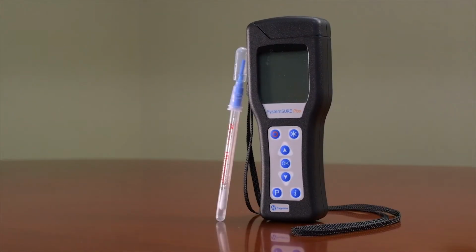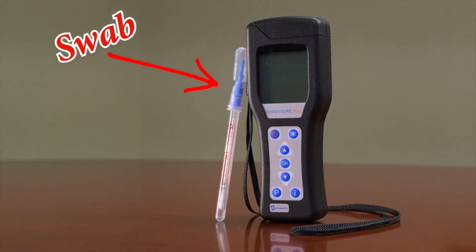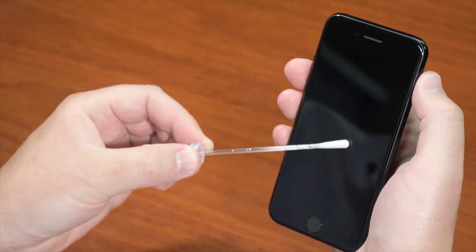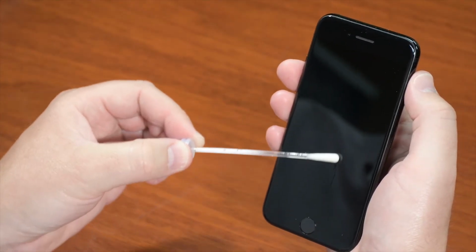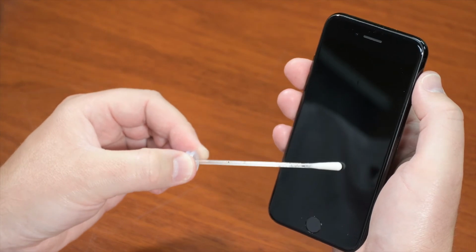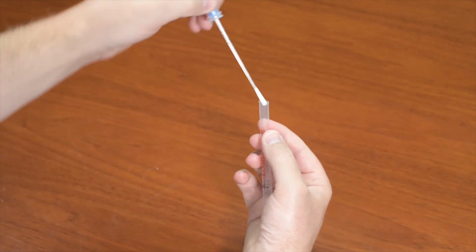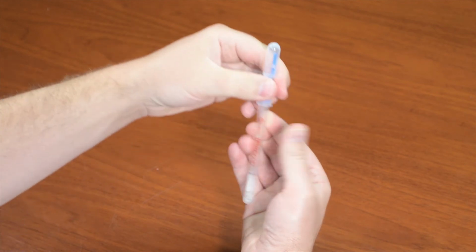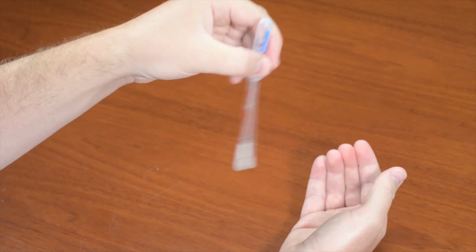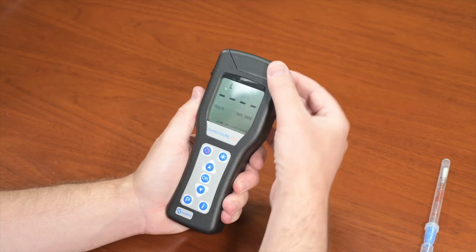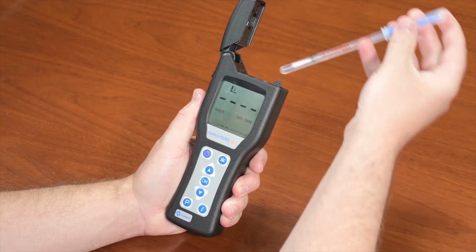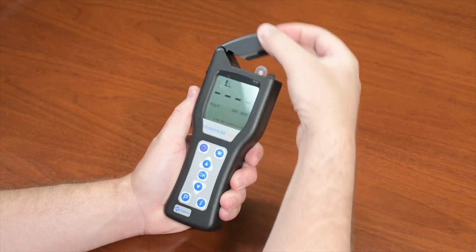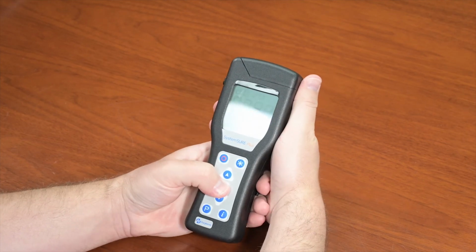The functionality is simple. Just take the swab provided by the company that supplies your ATP reader, wipe the swab along a surface area that often comes in touch with human contact, place the swab back in the casing, crack the liquid capsule at the end and swirl the plastic casing to properly coat the swab, and finally place the casing in the ATP reader, and within 15 seconds you have a reading of the contamination level on your sample surface.